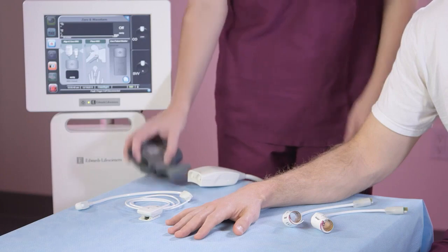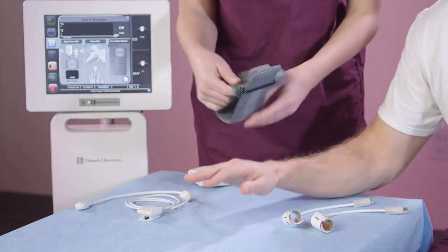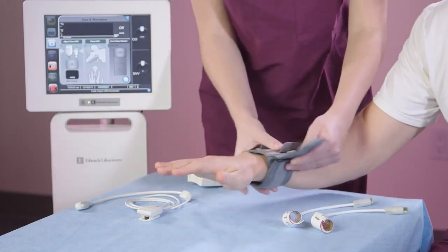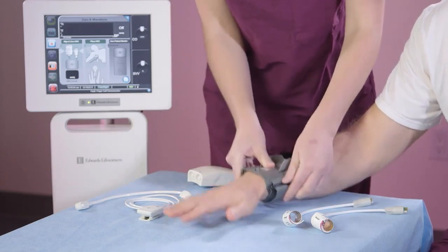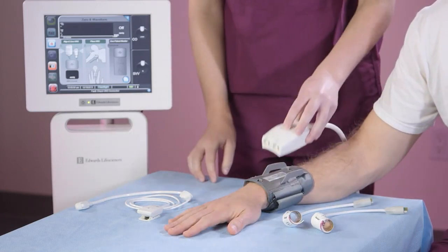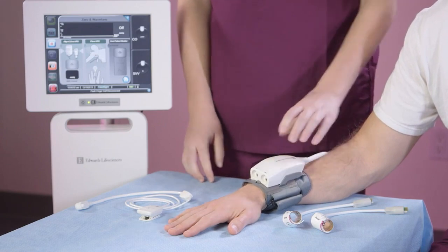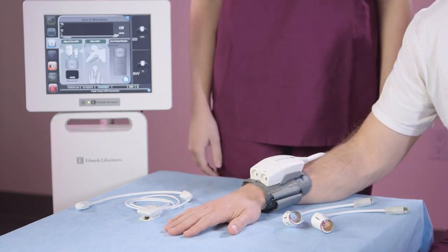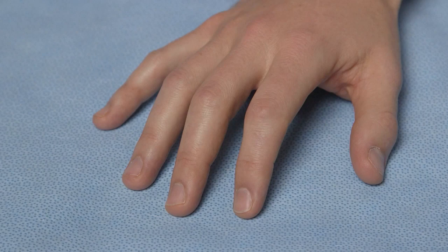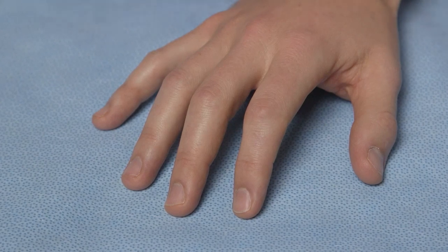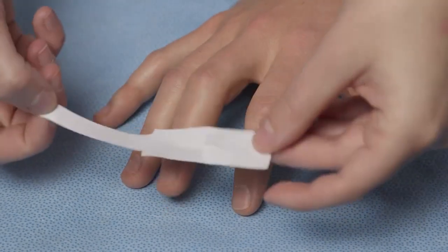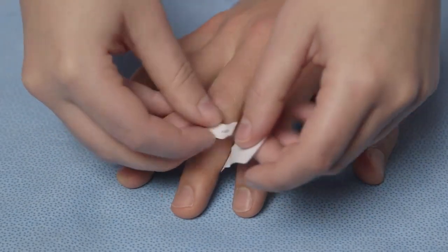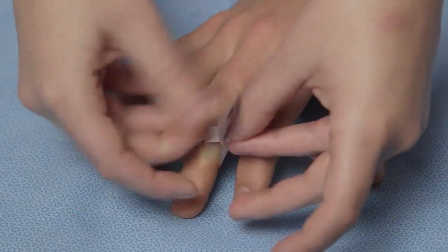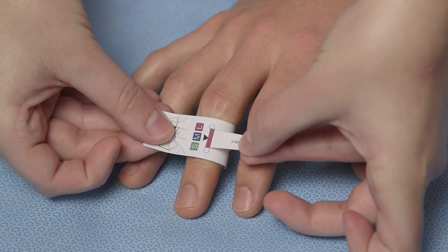Next, wrap the wristband around the patient's wrist with the two click frame guides facing away from the fingers. Attach the pressure controller to the wristband with the finger cuff ports facing the patient's fingers. You will hear a click when the pressure controller is securely connected. Measure the patient's finger girth with the sizing tool to determine the proper size finger cuff to be used. Wrap the sizing tool around the index, middle, or ring finger. The color that lines up with the slit corresponds to the cuff size for that particular patient.